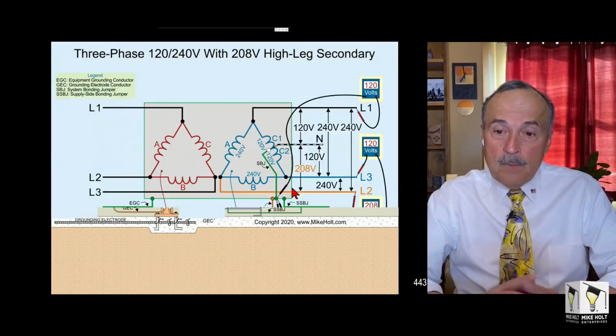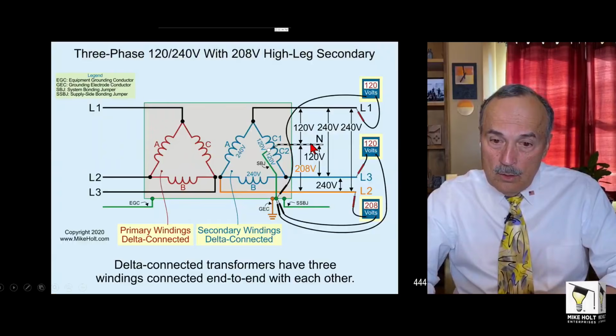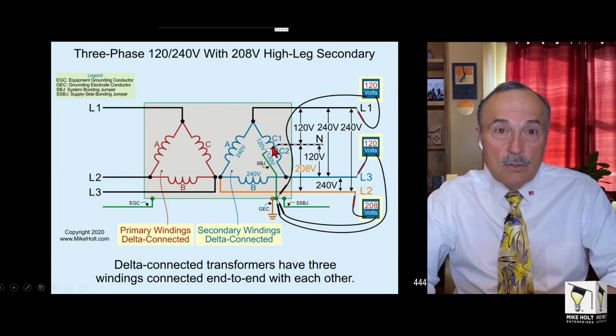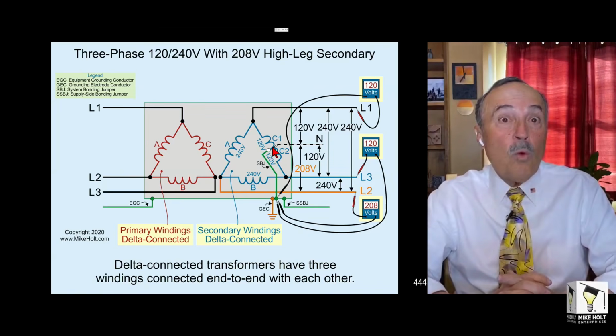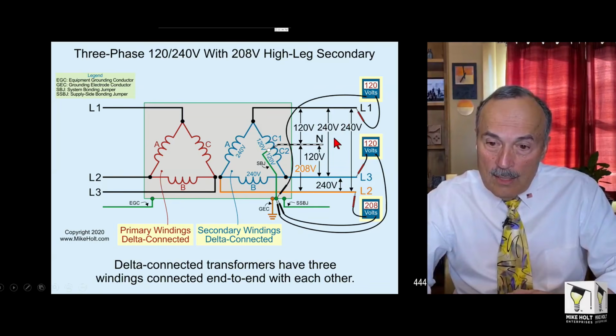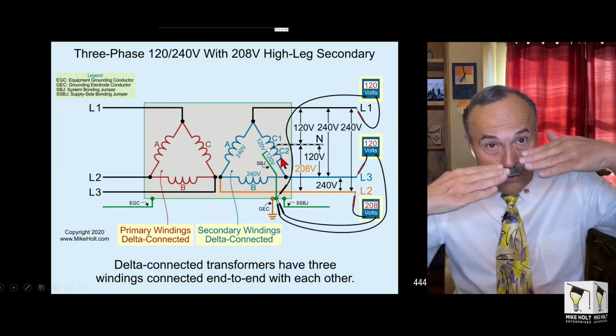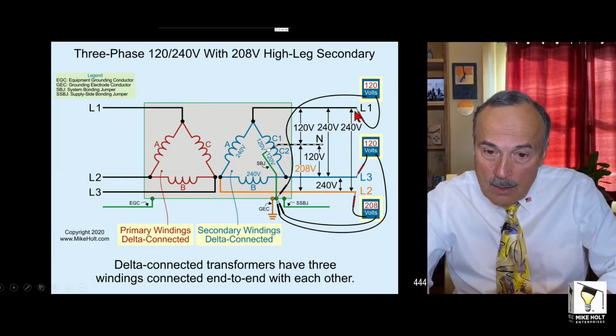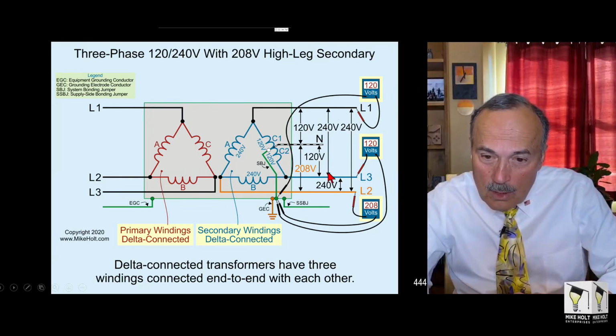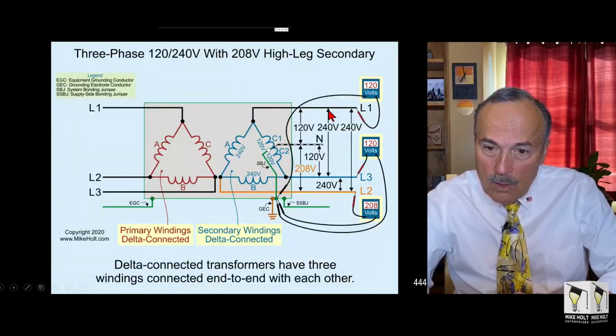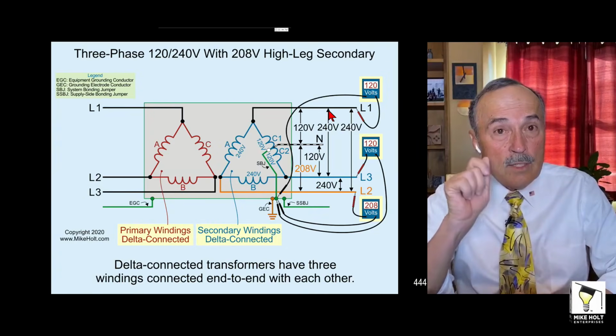So here's your high leg. Voltage from line 1 to the neutral or to the ground point is 120. Line 3, with the voltmeter, to the ground point, which is the same thing as to the neutral point, that half of a winding, is 120. Voltage between line 1 and line 3, which is right here, well, that's 120 plus 120 straight, additive directly. So line 3 and line 1 is 240. So line 1 to line 3 is 240.